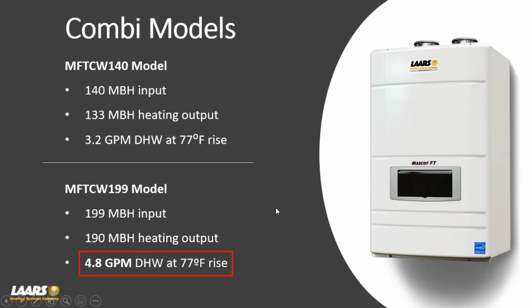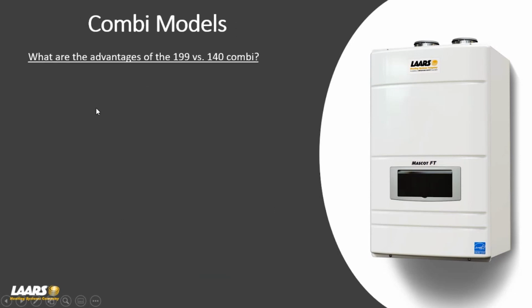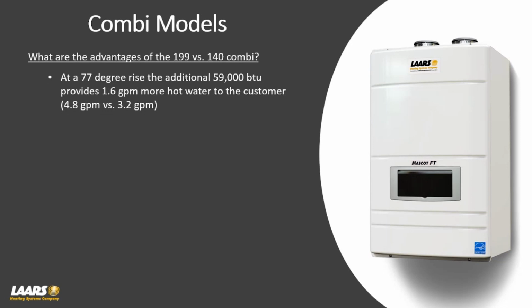And why I highlighted this is a lot of contractors ask, what are the advantages of selling a 199 over a 140? Maybe they only need 120 or 140,000 BTUs for the heating. So I threw in a couple of bullet points here that I'd like to talk about. First of all, a 199 at the 77 degree rise, you get an additional 59,000 BTUs. And that provides 1.6 gallons per minute of hot water to the customer. So it's 4.8 versus 3.2.